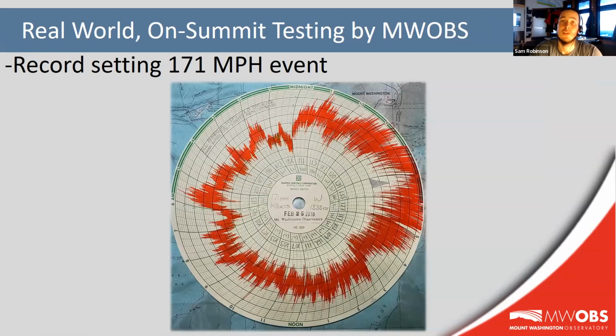So the Mount Washington Observatory crew was then able to get that pressure transducer back, reinstall everything into the anemometer, and reinstall it on the summit on February 23rd of 2019. And that was just in time to measure the 171 mile per hour gust on February 25th of 2019, which was actually a new record for the month. And it's important to note that pitot 19 also recorded a gust of 171 at the same moment, which was definitely a good sign for the initial integrity of this new pitot.